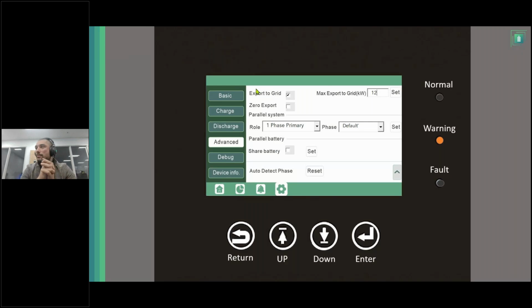If you do not want to export, let's say zero net export, then at that time it's going to take the force discharge power and discharge to the loads. But if I say I want to force discharge 8 kW, but I'm really using 4 kW, it's going to just discharge 4 kW into your loads.